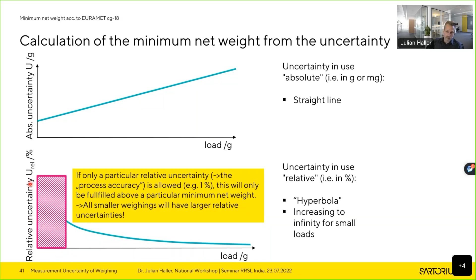And that means if you, for your processes, have a limit and say, I do not want the relative uncertainty of my measurement result to be bigger than 1%, 0.1%, whatever your requirement is, then it's quite easy to say that you have to weigh in at least this much. And this is the concept of minimum net weight. If you want to have the relative uncertainty smaller than this value, you have to weigh in that much. Every bigger load will have a smaller relative uncertainty, and every smaller load will have a bigger relative uncertainty.